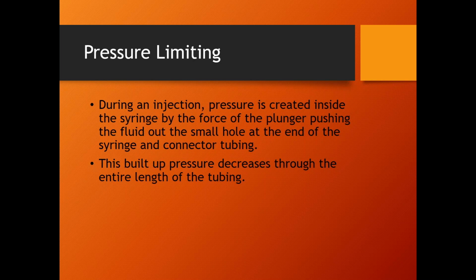Now, the one factor that determines 99% of how much pressure is going to get built up in the syringe is the flow rate. The faster the injection, the greater the pressure in the syringe. All right, so this is a 200 milliliter syringe, and let's say I set up an injection for 1 milliliter per second for 200 seconds. That means it would take 3 minutes and 20 seconds to shove all the fluid very, very slowly out of this syringe through this little tube. That's almost no pressure at all getting built up inside the syringe.